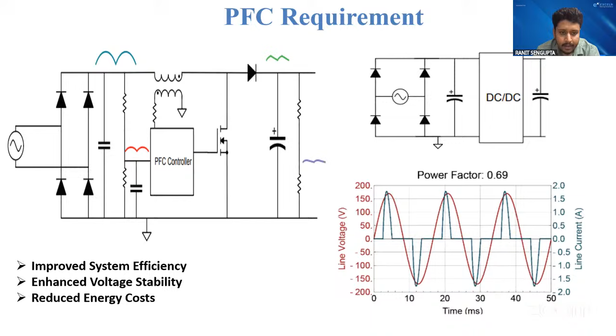So due to this high frequency switching, it affects the input current as well. That is why THD, meaning total harmonic distortion - how much distorted your input sinusoidal waveform is - they have given less than 3%. Mostly a good design should have less than 5% THD, so 3% is good.